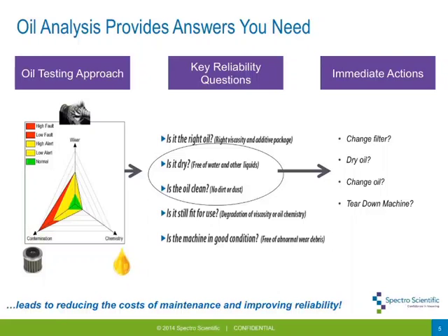Oil analysis provides a huge amount of data — on any typical oil analysis report from a lab, you can get anywhere from 30 to 60 individual data points, depending on what type of testing you're doing. But what you're really trying to do with all that data is answer a couple of key reliability questions. From an oil analysis perspective, those questions are: Have I got the right oil present? Is it dry? Is it clean? Is it still fit for further use? And is the machine in okay condition — do I need to do anything?